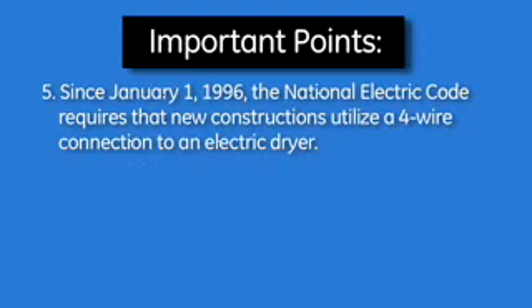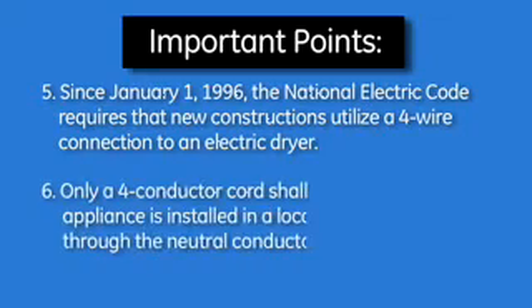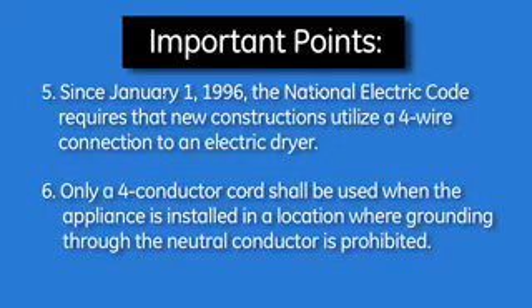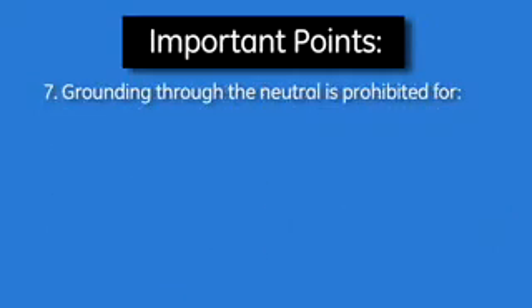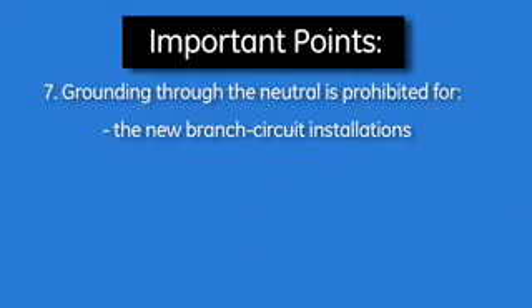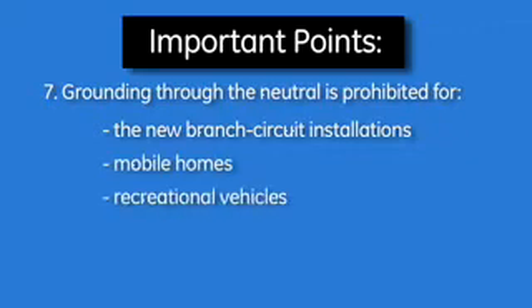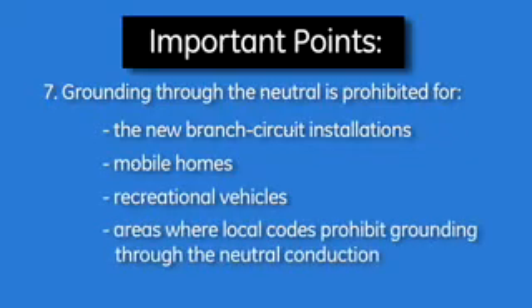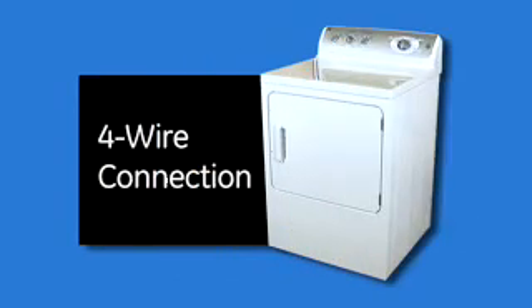Since January 1st, 1996, the National Electric Code requires that new constructions utilize a 4-wire connection to an electric dryer. Only a 4-conductor cord shall be used when the appliance is installed in a location where grounding through the neutral conductor is prohibited. Grounding through the neutral is prohibited for new branch circuit installations, mobile homes, recreational vehicles, and areas where local codes prohibit grounding through the neutral conductor. To properly install the 4-wire connection, follow these steps.